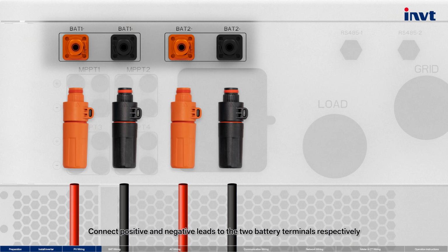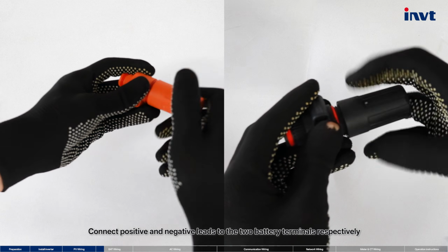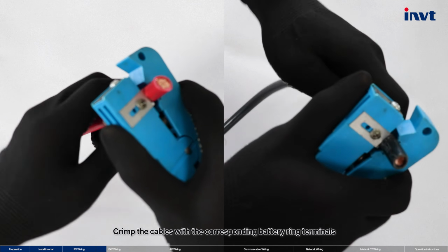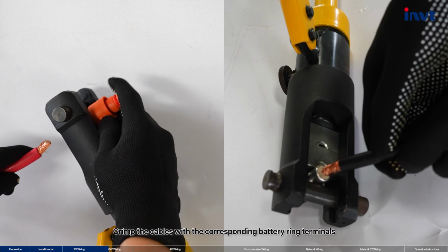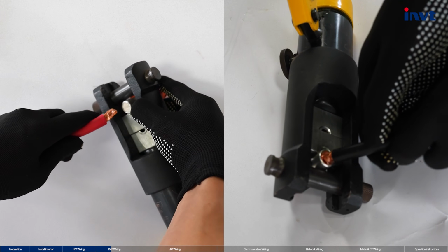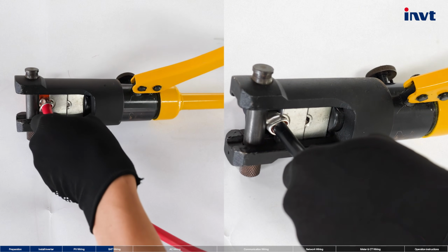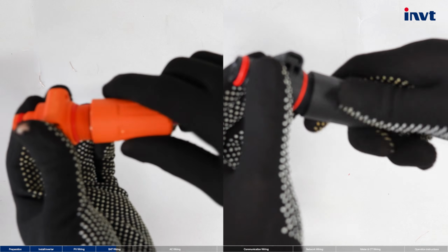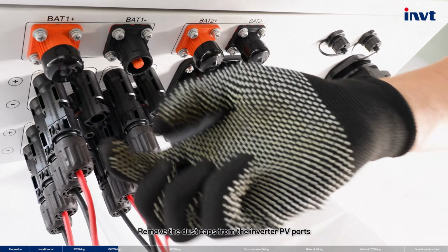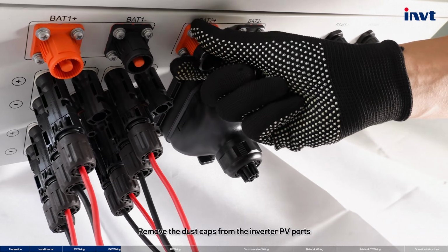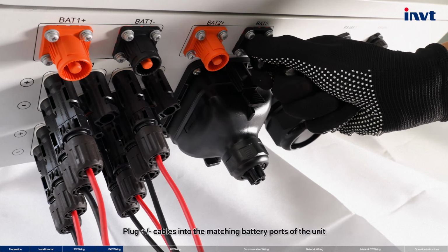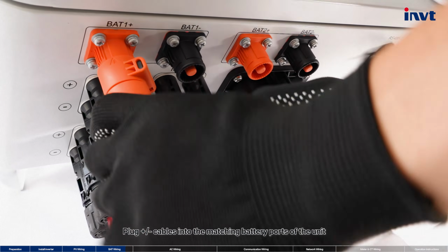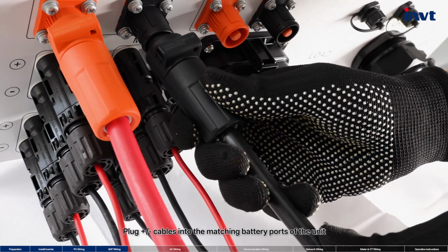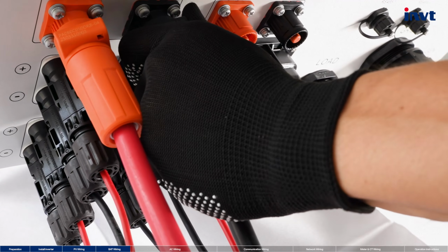Connect positive and negative leads to the two battery terminals respectively. Crimp the cables with the corresponding battery ring terminals. Remove the dust caps from the inverter PV ports. Plug positive-negative cables into the matching battery ports of the unit. Press firmly until you hear a click.